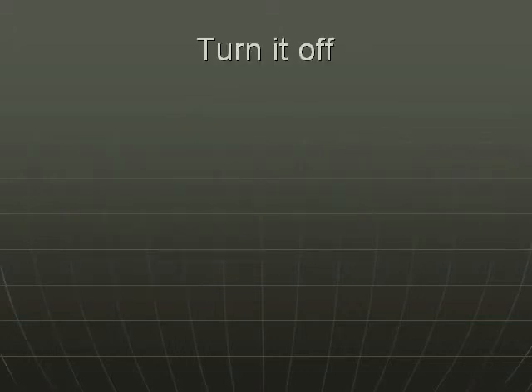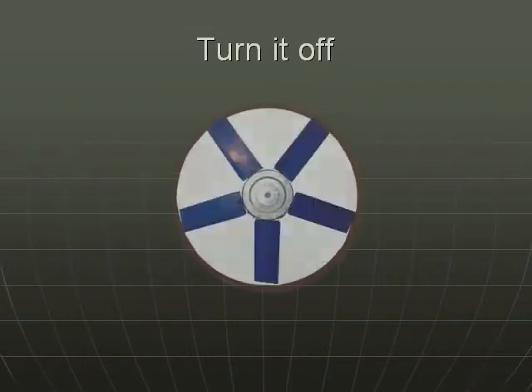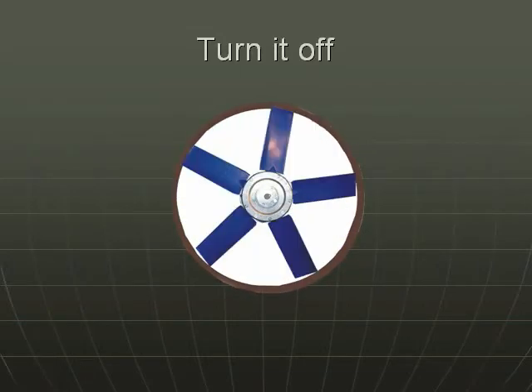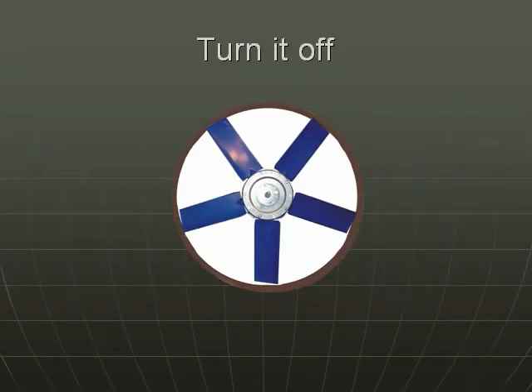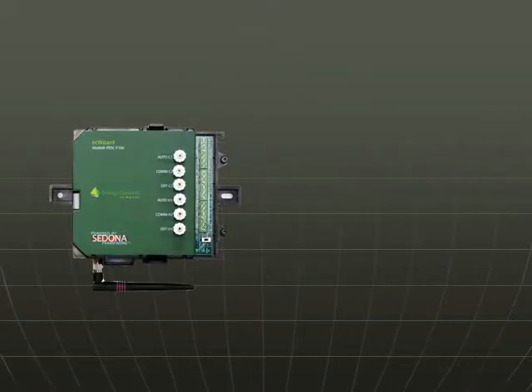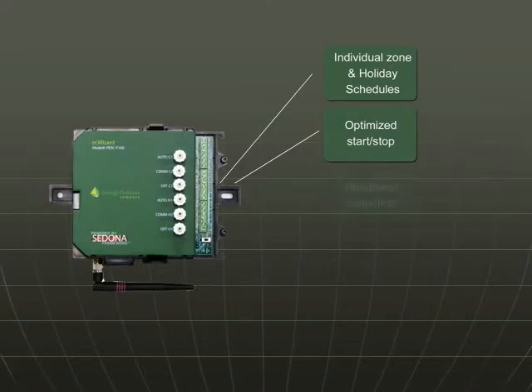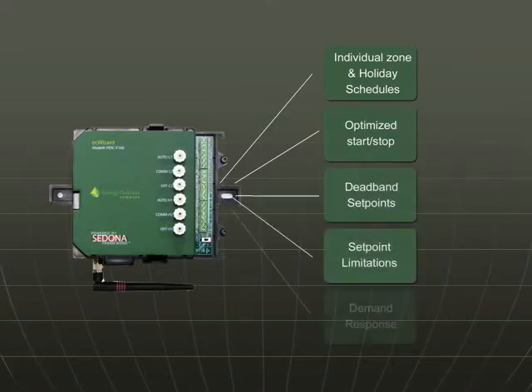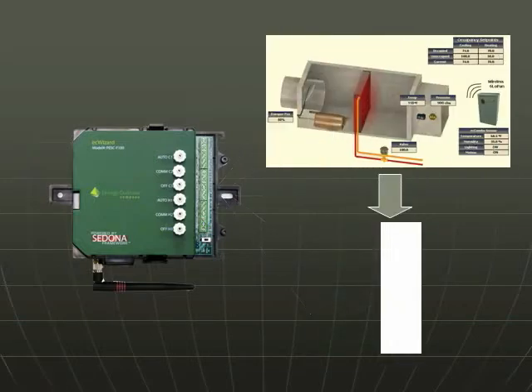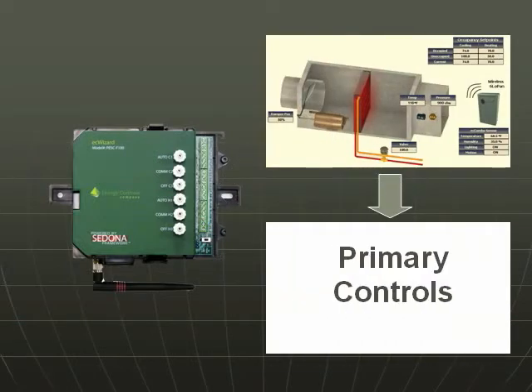The ecWizard uses an old, established sequence of operations for energy savings. It's called Turn It Off. The ecWizard provides individual zone scheduling, holiday schedules, optimized start-stop, deadband setpoints, setpoint limitations, and demand response. It also gives zone temperature monitoring commands to the primary system for coordinating comfort and energy savings.